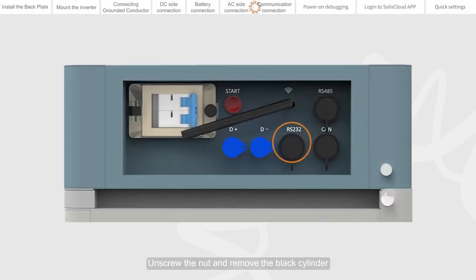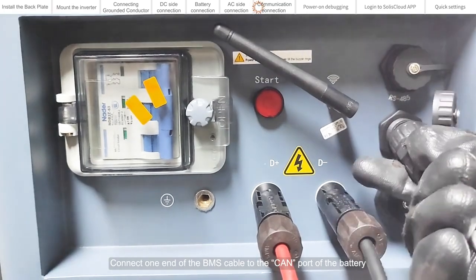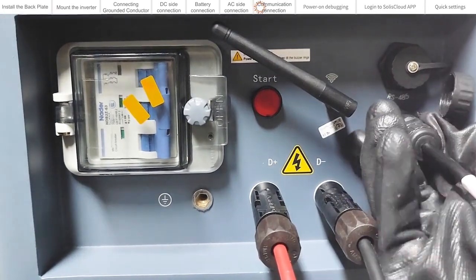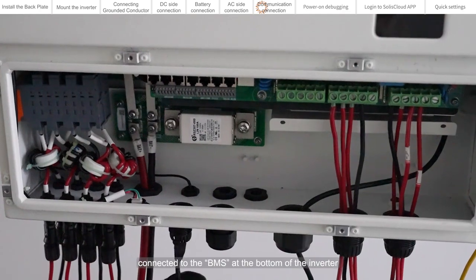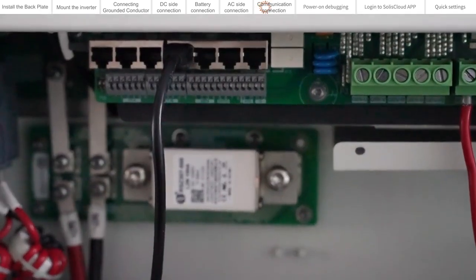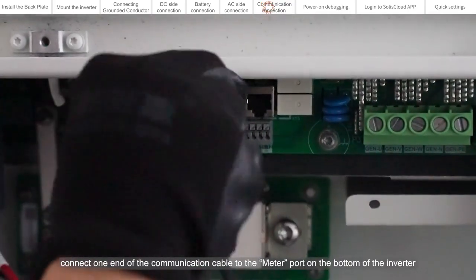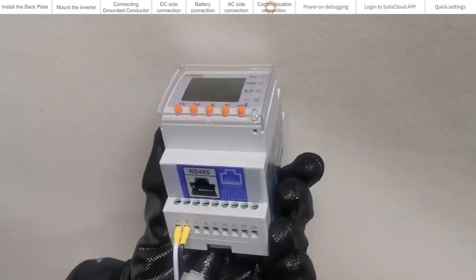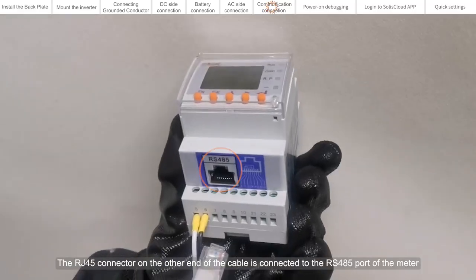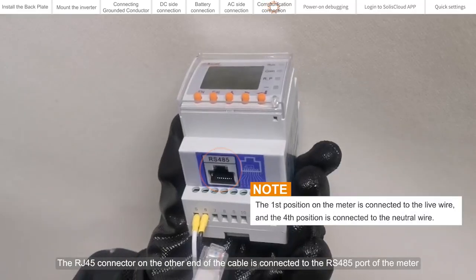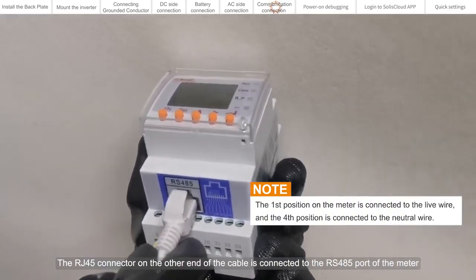Communication connection. Unscrew the nut and remove the black cylinder. Connect one end of the BMS cable to the CAN port of the battery. Connected to the BMS at the bottom of the inverter. In the same way, connect one end of the communication cable to the meter port on the bottom of the inverter. The RJ45 connector on the other end of the cable is connected to the RS485 port of the meter.